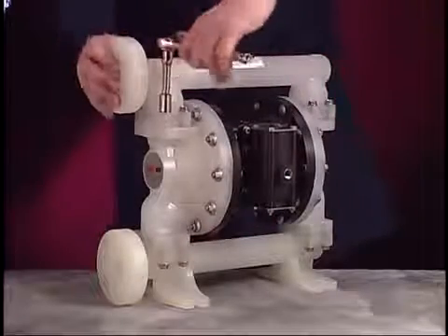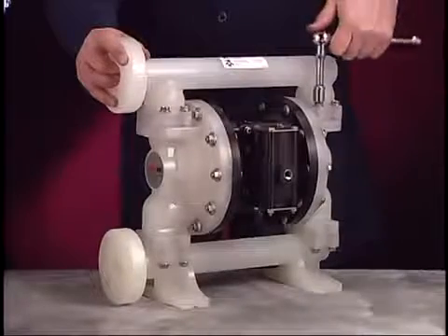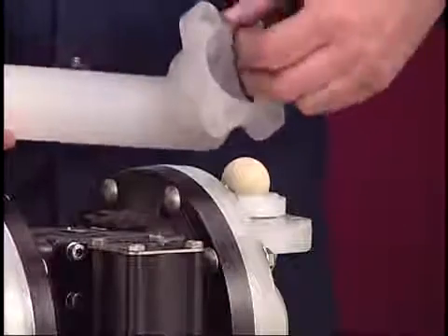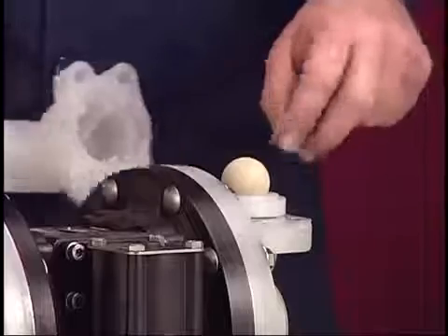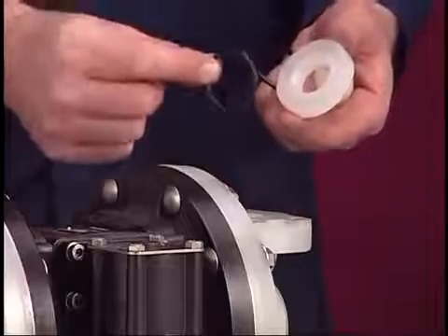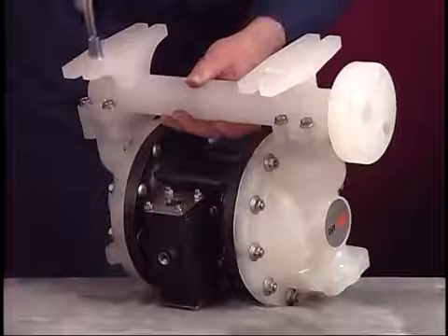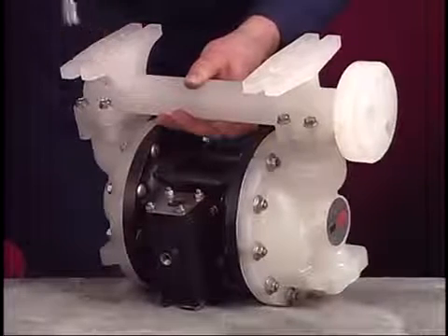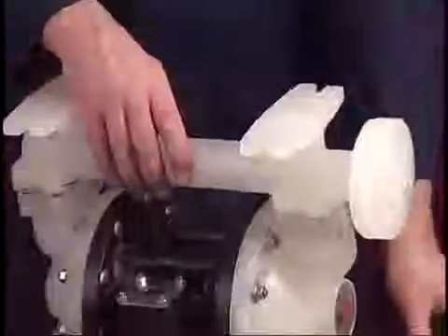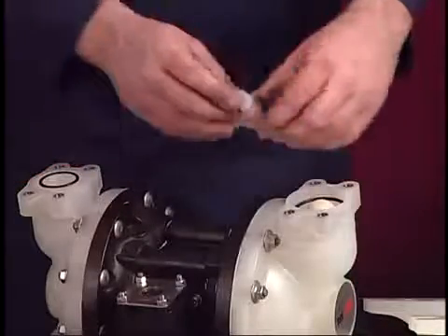Use a 1/4-inch socket to remove the eight screws that hold the outlet manifold in place. Lift the manifold, then remove the ball check, seat, and two O-rings. Be careful not to damage the sealing point of the seat. Rotate the pump so that the lower manifold can be reached. Use the 1/4-inch socket to remove the lower inlet manifold. Pull the O-rings, seats, and ball checks from the fluid caps.